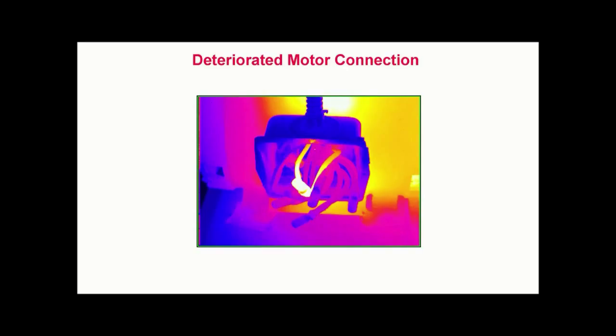Because all of the motor leads are under the same load, we would expect even heating throughout each conductor and its connections. In this image, we see localized heating, shown in white, at one of the splices, which typifies a loose connection.